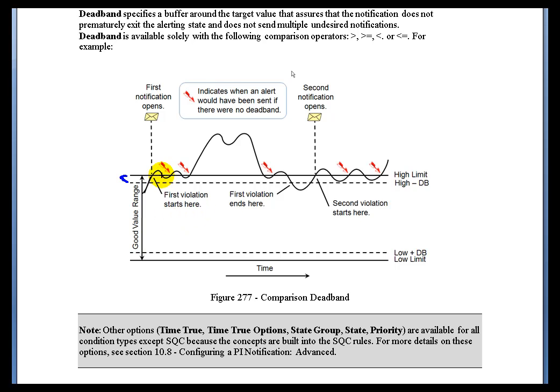For example, if you look at this point right here, that's where we do the initial Alarm State, but because of the Deadband, when we go back out of Alarm at this point right there, we're not going to go out of Alarm because we haven't crossed the Deadband yet. So the Deadband is a value below which we must come before we go out of an Alarm State.